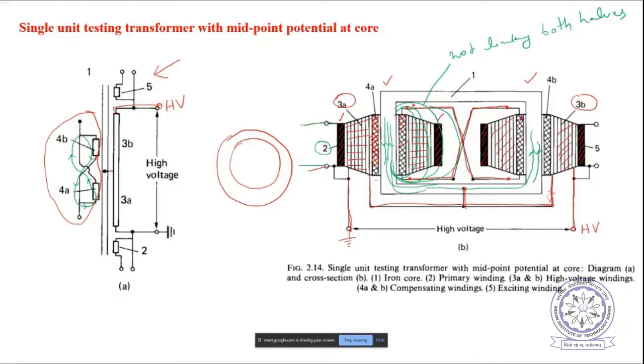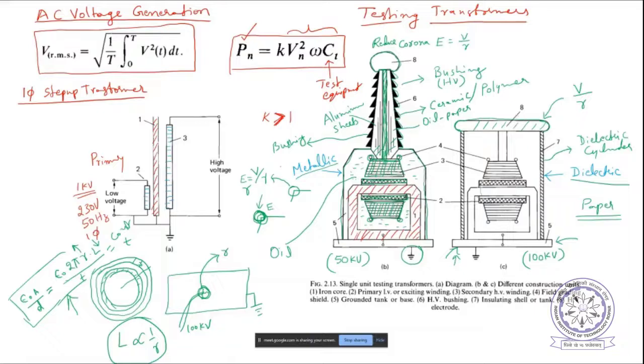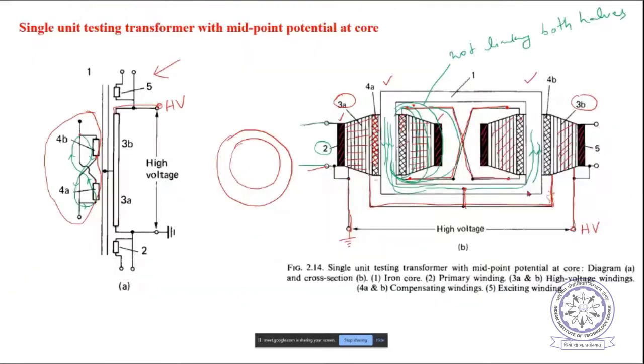Therefore we get the midpoint connected exactly to the core, and each winding is equally stressed. Now what is the advantage of going into two halves? Each winding is similar to the single winding of this transformer, and from this core level to here roughly about 100 kilovolts we can obtain. That is the physical limitation of making a single unit transformer. By making two halves and two legs, we could achieve 100 kilovolts on one leg and 100 kilovolts on another leg, so total around 200 kilovolts can be obtained.